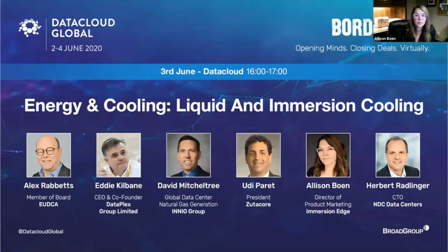As I said yesterday, we've got plenty of room in the sandbox for immersion cooling with the densities we're now seeing. Look at what NVIDIA put out yesterday, that supercomputer in a box. For just one rack alone, that's a minimum of 36 kW and starts there. That's going to bring some great savings just for equipment, but again, that's very high density in a very small footprint.